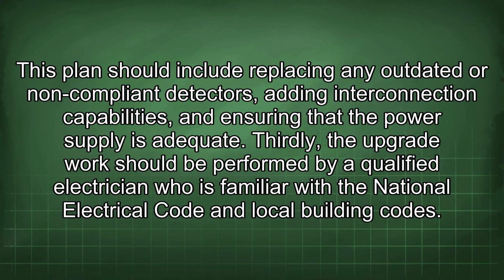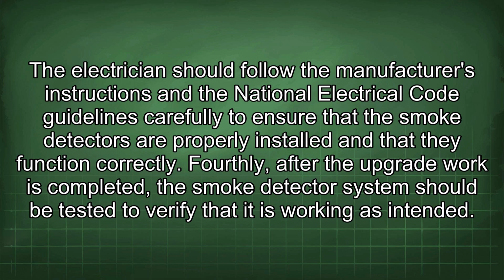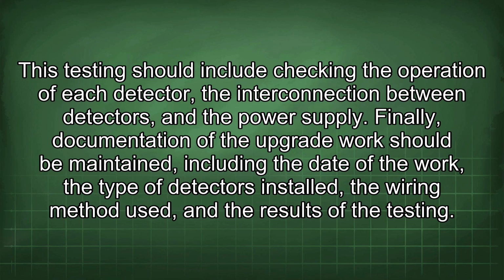adequate. Thirdly, the upgrade work should be performed by a qualified electrician who is familiar with the National Electrical Code and local building codes. The electrician should follow the manufacturer's instructions and the National Electrical Code guidelines carefully to ensure that the smoke detectors are properly installed and that they function correctly. Fourthly, after the upgrade work is completed, the smoke detector system should be tested to verify that it is working as intended. This testing should include checking the operation of each detector, the interconnection between detectors, and the power supply.